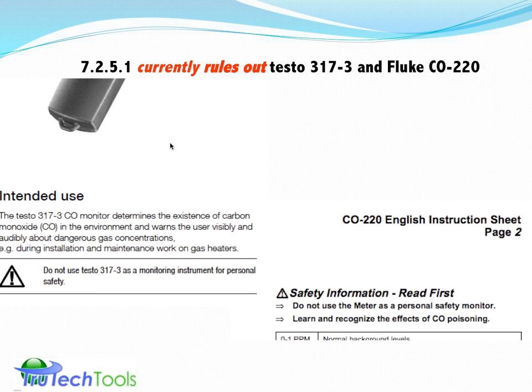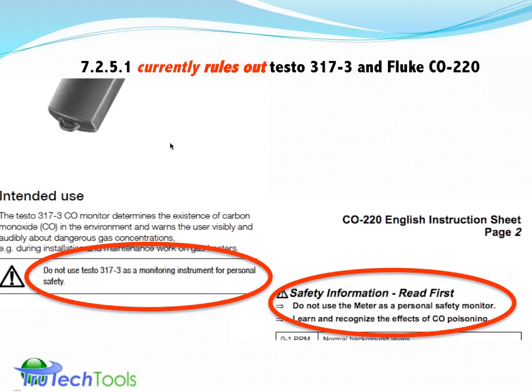This one standard here would actually rule out the use of a Testo 317-3 or a Fluke CO 220, for the reason that the manufacturers actually say do not use for personal safety, do not use as a personal safety monitor. These are excerpts from the Testo and the Fluke instruction manuals. So I think BPI may be going back and looking at this statement to see if that's really what was intended.